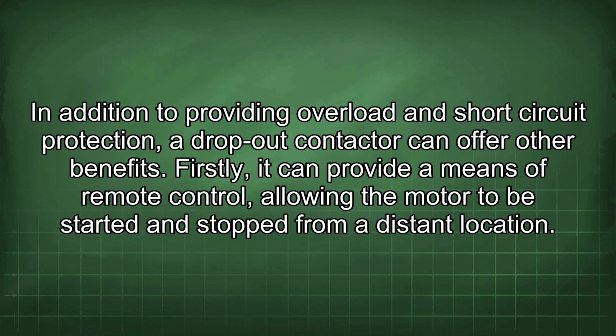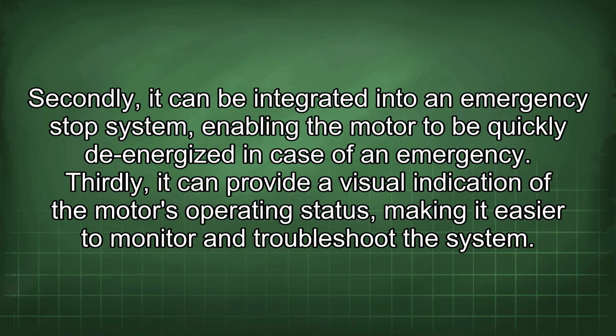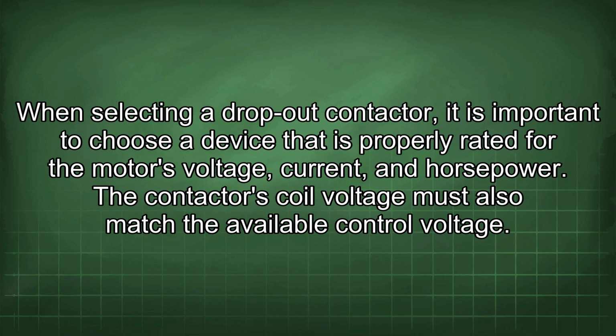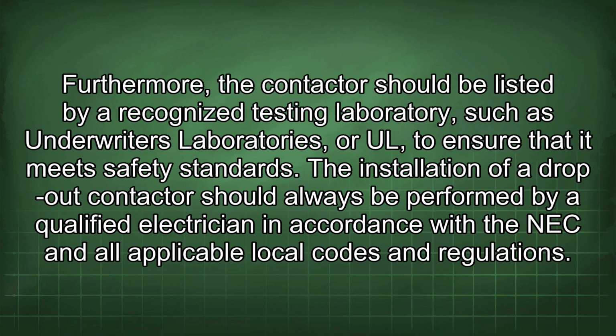In addition to providing overload and short-circuit protection, a dropout contactor can offer other benefits. Firstly, it can provide a means of remote control, allowing the motor to be started and stopped from a distant location. Secondly, it can be integrated into an emergency stop system, enabling the motor to be quickly de-energized in case of an emergency. Thirdly, it can provide a visual indication of the motor's operating status, making it easier to monitor and troubleshoot the system. When selecting a dropout contactor, it is important to choose a device that is properly rated for the motor's voltage, current, and horsepower. The contactor's coil voltage must also match the available control voltage. Furthermore, the contactor should be listed by a recognized testing laboratory, such as Underwriters Laboratories, or UL, to ensure that it meets safety standards.